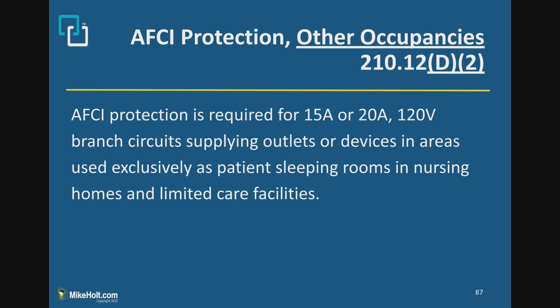D2 requires AFCI protection for 15 and 20 amp, 120 volt branch circuits supplying outlets or devices in areas used exclusively as patient sleeping rooms in nursing homes and limited care facilities. This is not a change — it was simply moved from the previous location where guest rooms and guest suites were combined with sleeping rooms.